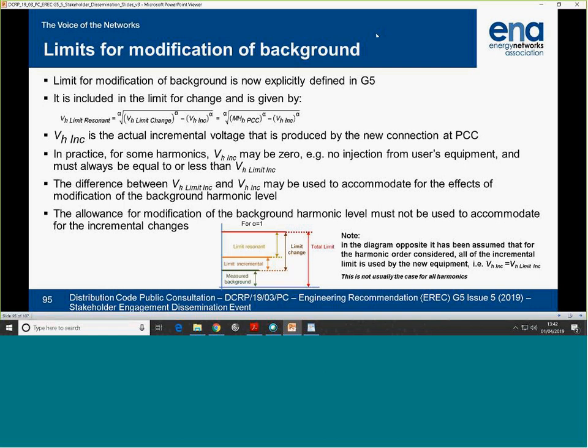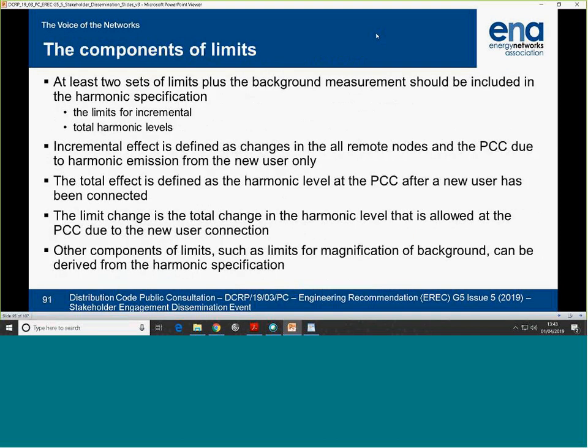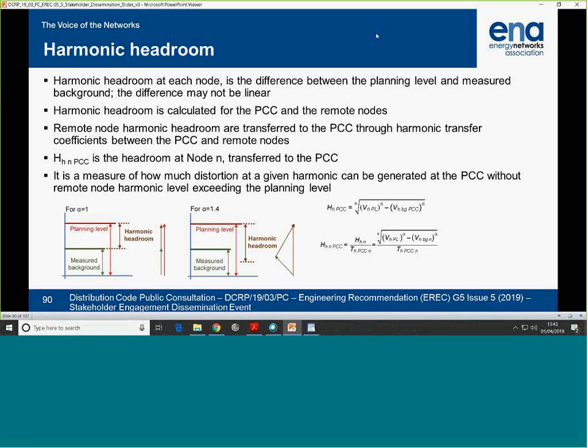Question? Yep. To calculate incremental, do you take into account the effect of the resonance, or is it only the injection from the equipment? The effect of resonance, the phase resonance, would be inherent in this. In resonance, the transfer coefficients would be very high. But that is between the PCC and another node. But if you have a resonance within the system that amplifies, not the background, but the injection from the unit, let's say from a wind turbine, will that be taken into account in this?